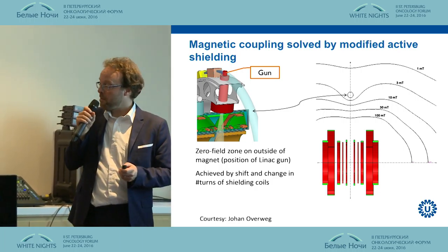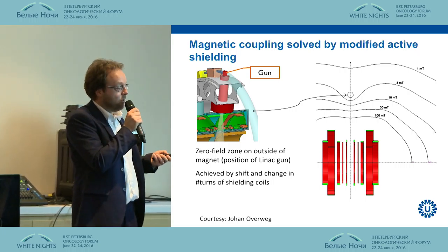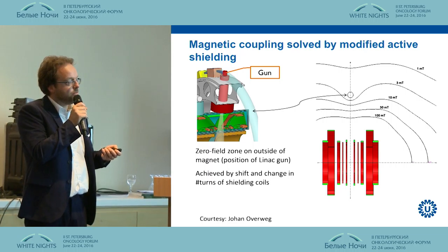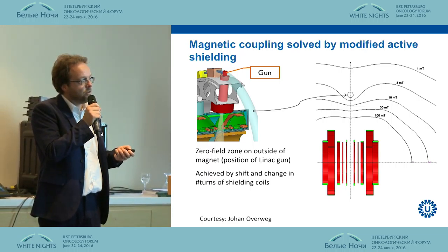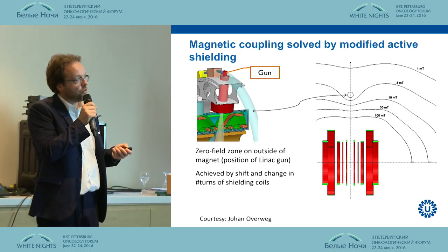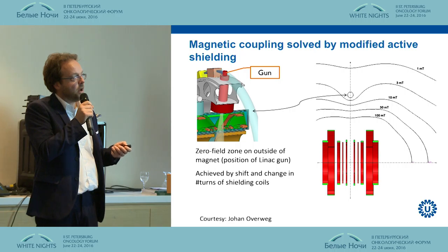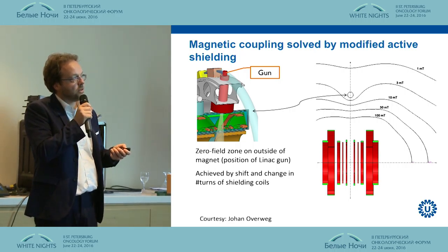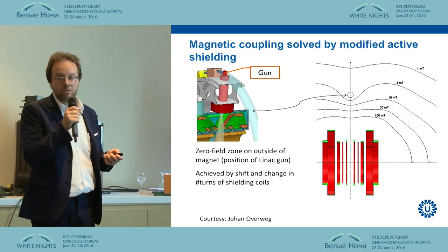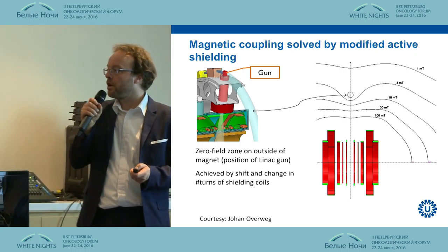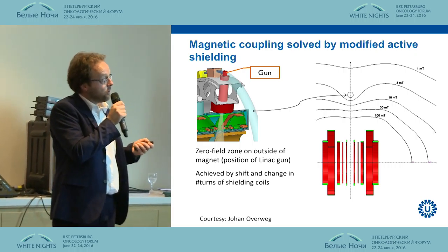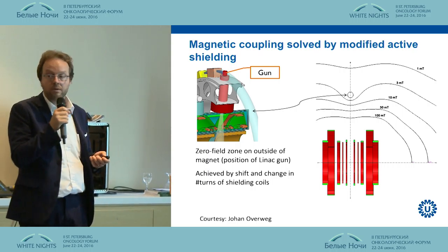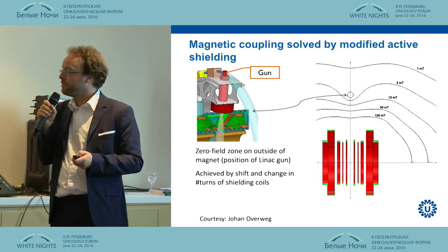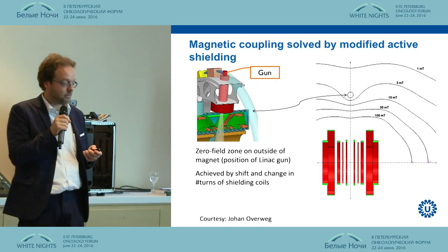Somebody from Philips came up with a very smart idea - Johan Overweg from Philips Hamburg. He said, okay, we can just slightly modify the design of the superconducting coils such that we get a sort of sweet spot in the middle where the field is actually very low. This is outside the scanner, and here you see there's a local minimum in the magnetic field because of this geometrical layout of the superconducting coils, where the field is almost zero. That's our sweet spot - there we put our accelerator, rotating through this sweet spot, so it doesn't feel the magnetic field of the MRI scanner.